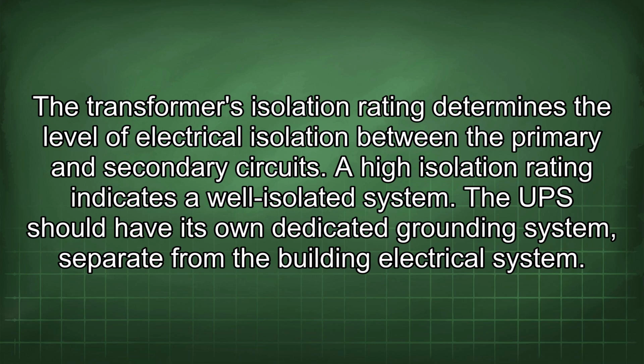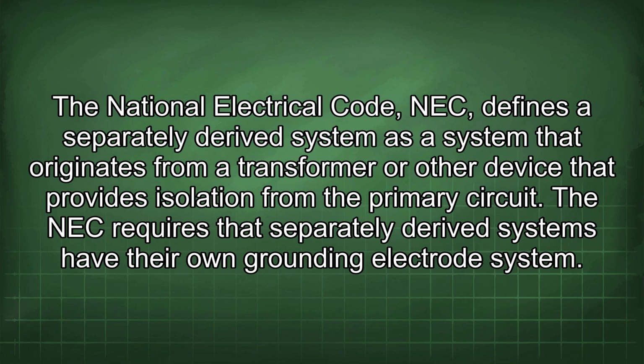A high isolation rating indicates a well-isolated system. The UPS should have its own dedicated grounding system, separate from the building electrical system. The National Electrical Code, NEC, defines a separately derived system as a system that originates from a transformer or other device that provides isolation from the primary circuit. The NEC requires that separately derived systems have their own grounding electrode system.